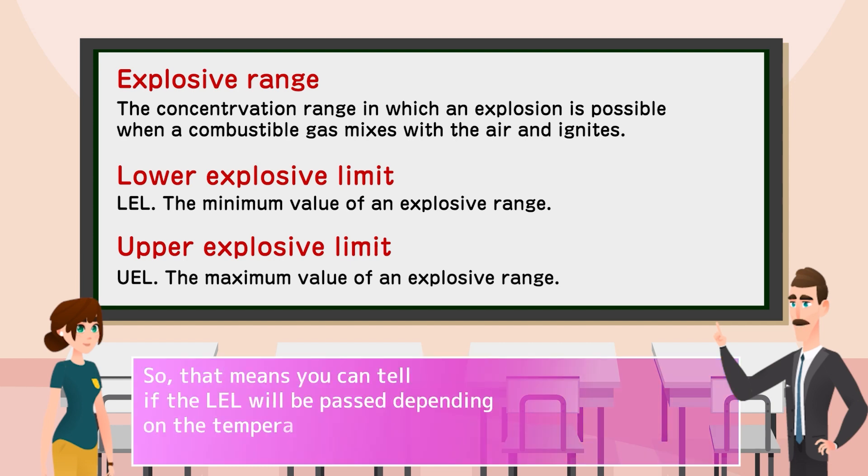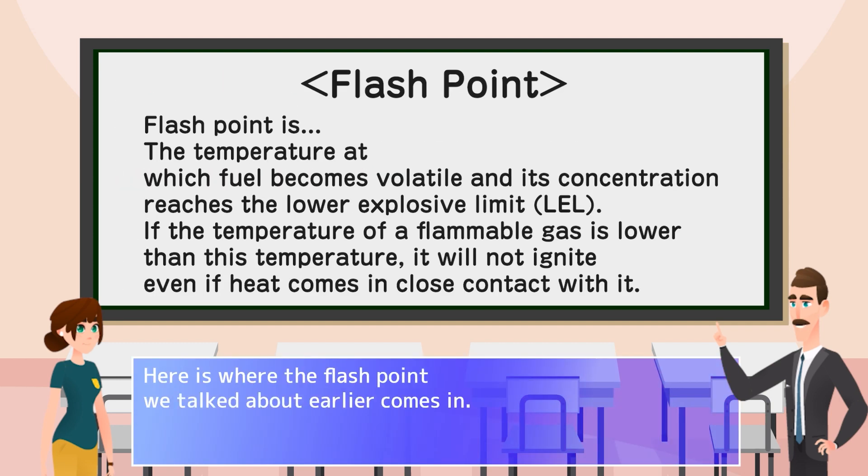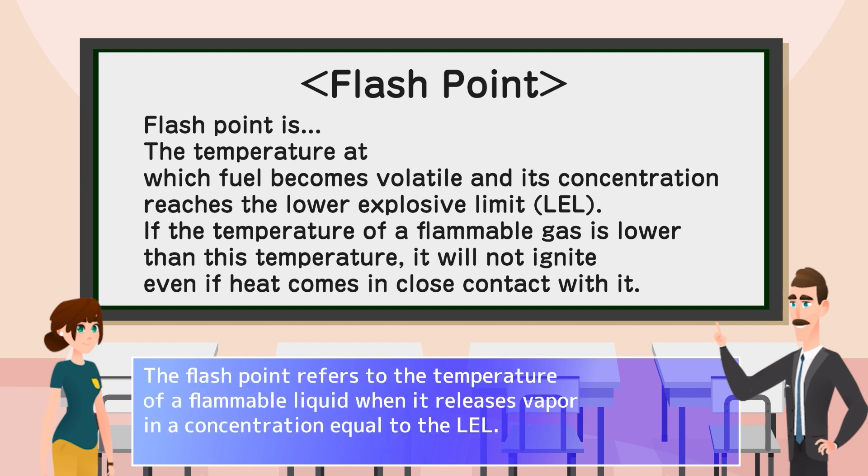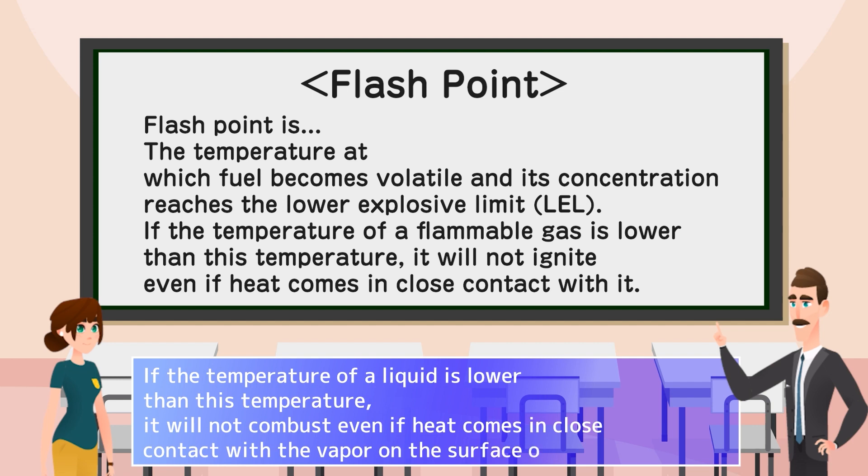So, that means you can tell if the LEL will be passed depending on the temperature. Here is where the flash point we talked about earlier comes in. The flash point refers to the temperature of a flammable liquid when it releases vapor in a concentration equal to the LEL. In other words, the temperature required for the flammable liquid to combust because of the heat. If the temperature of a liquid is lower than this temperature, it will not combust even if heat comes in close contact with the vapor on the surface of the liquid.